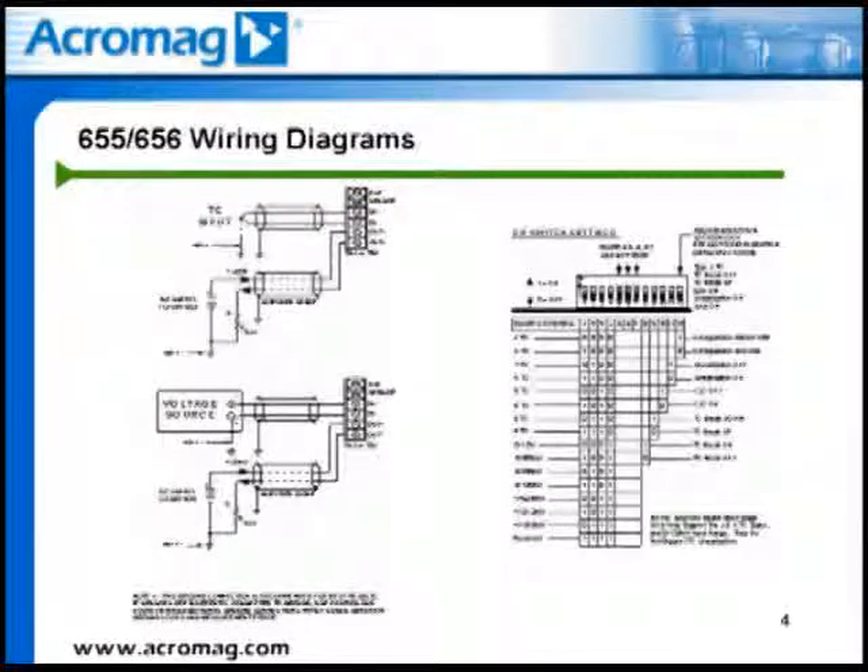Adjacent to the channel terminals is the set of DIP switches used to select input type for thermocouples or range for millivolts, enable or disable thermocouple break detection, set thermocouple break detection either upscale or downscale, turn cold junction compensation on or off, enable or disable linearization, and to lock or unlock the channel's configuration. Each channel on the 656T module can have its own DIP switch settings and is not dependent on or affected by the other channel.